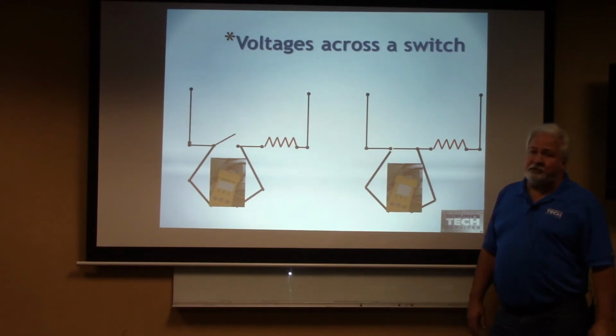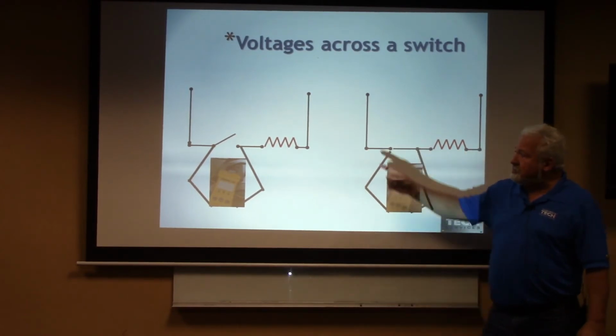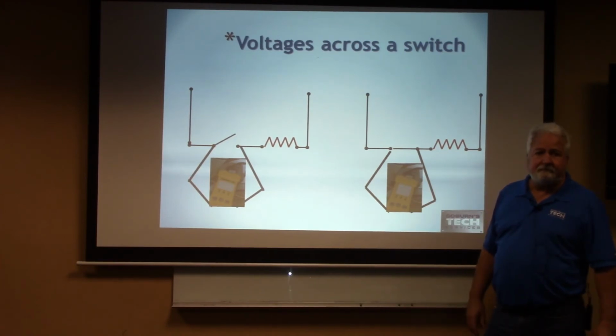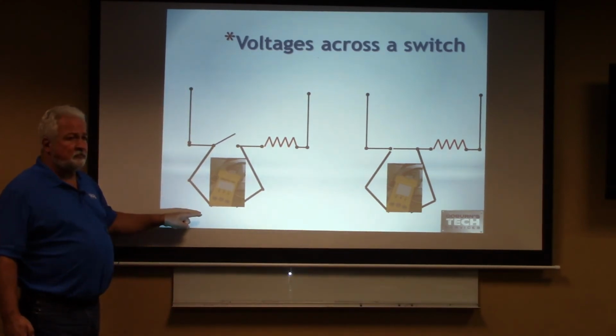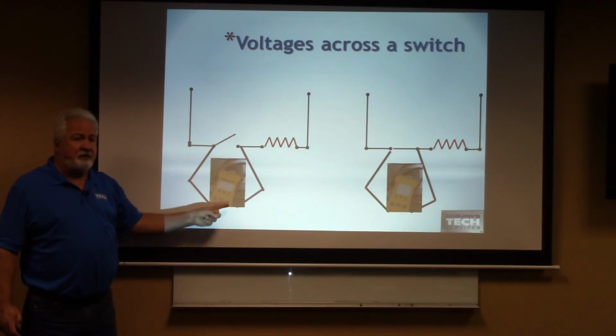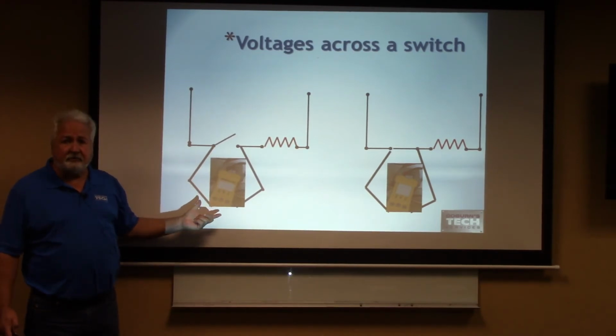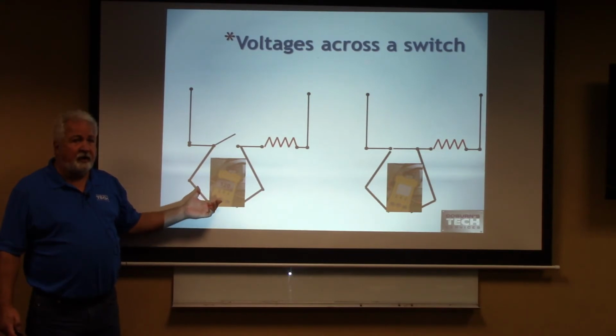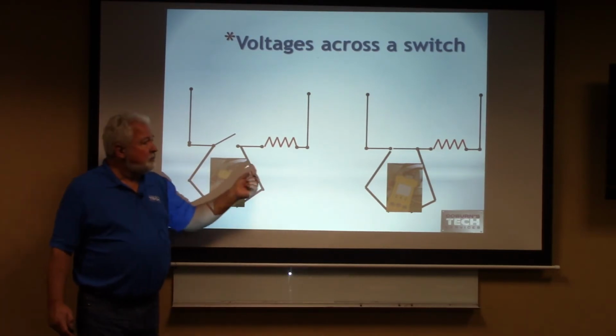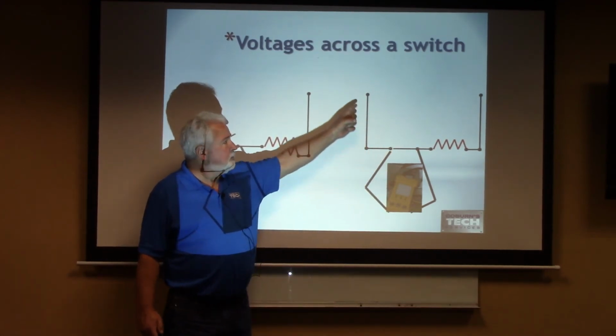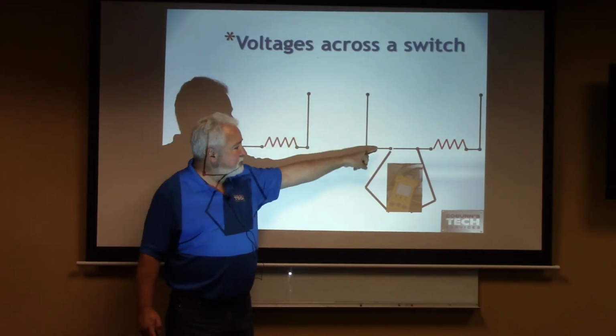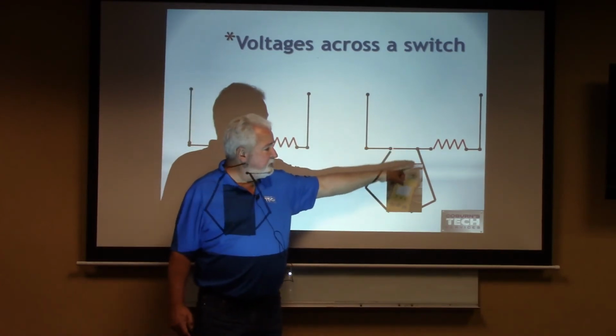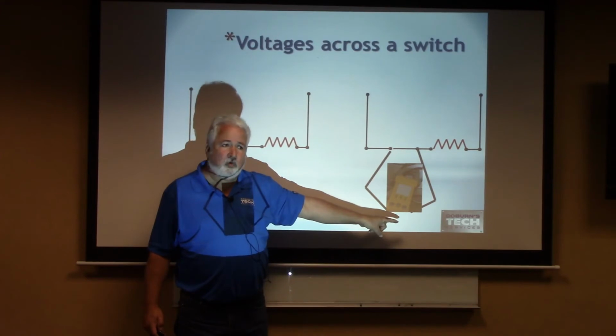So, voltage across a switch. I see this all the time. What would I read across that switch right there? Line voltage or control voltage. But it's open. Well, that's why you read it. Do I see L1 potential to my meter? Yes. Do I see the L2 potential to my meter? Good. If I see two different potentials, what am I going to read? The line voltage. Is everybody good with that? Across a switch, am I going to see the two different potentials across that switch? I'm going to see the L1 potential to here, and I'm going to also see the L1 potential to here. If I see L1 and L1, what is my meter going to read?